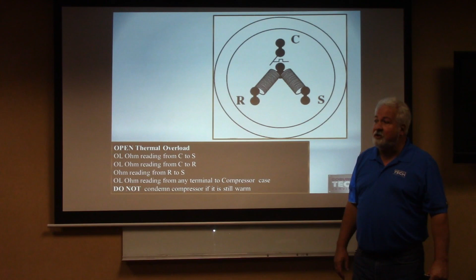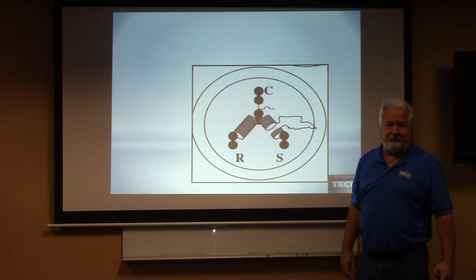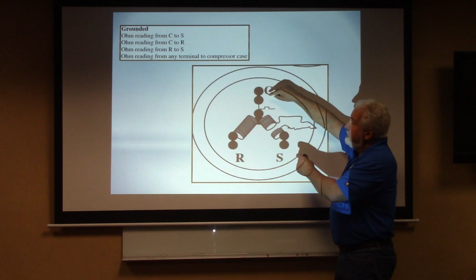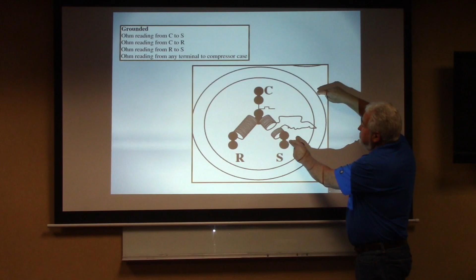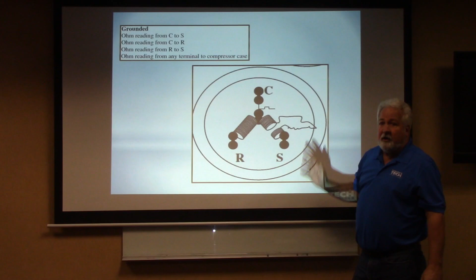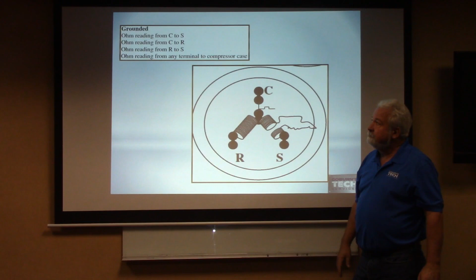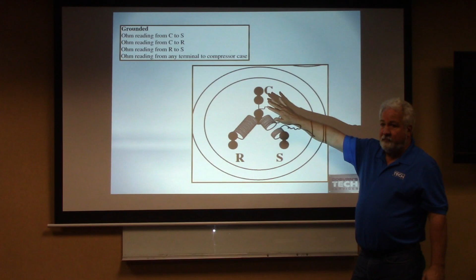Now what's happened? Part of our winding is actually touching that case, so now I have a grounded compressor. Ohm reading from common to start - will I have one? Is there a path? Yes, so I'll get an ohm reading. Will I get one from common to run? Yes. From run to start? Sure will. From start to the case? Yes. It might be any number of readings, but it's not going to be OL. In this case we have a grounded compressor.